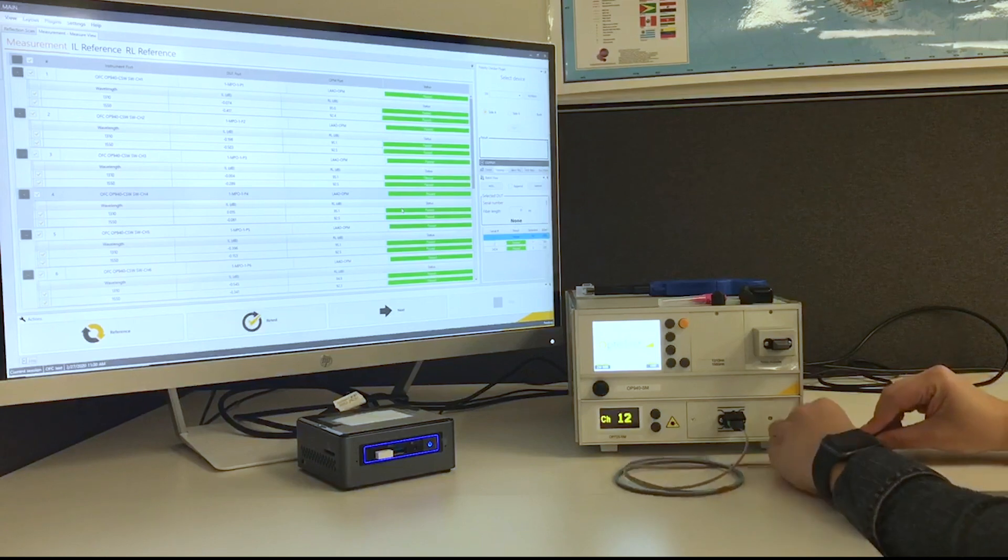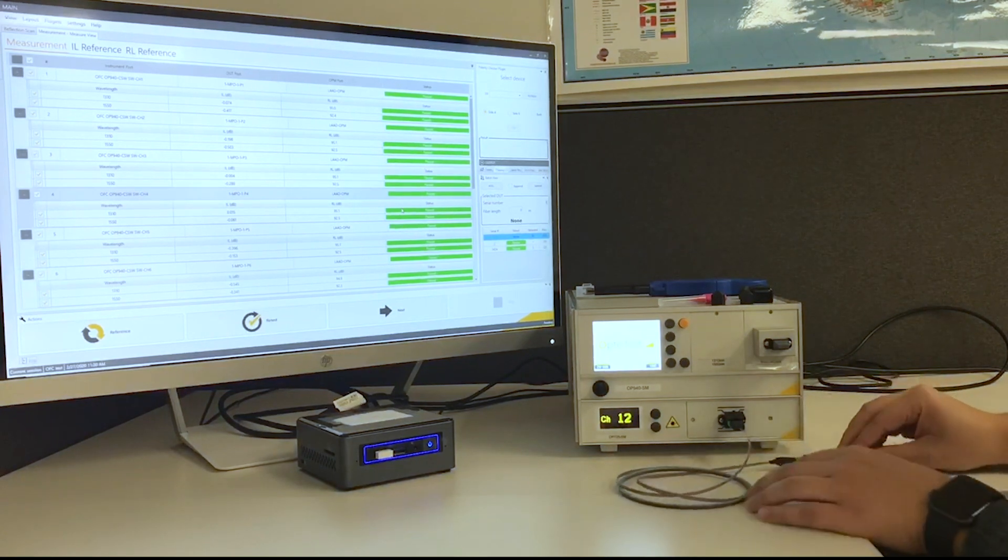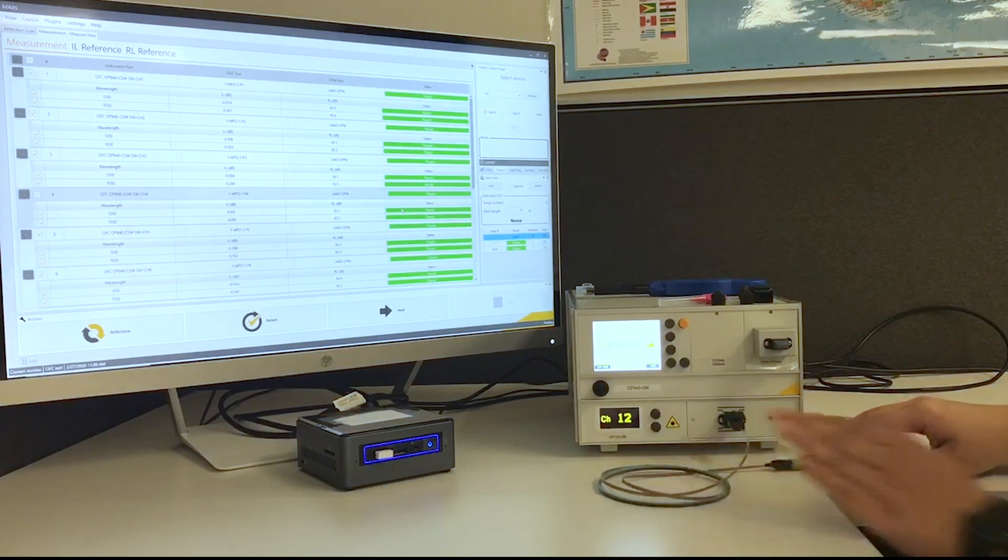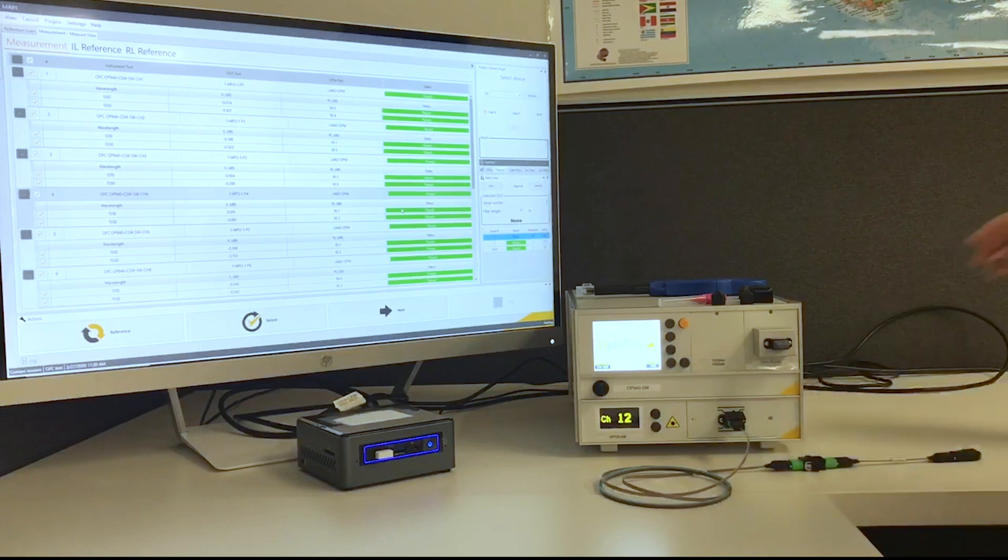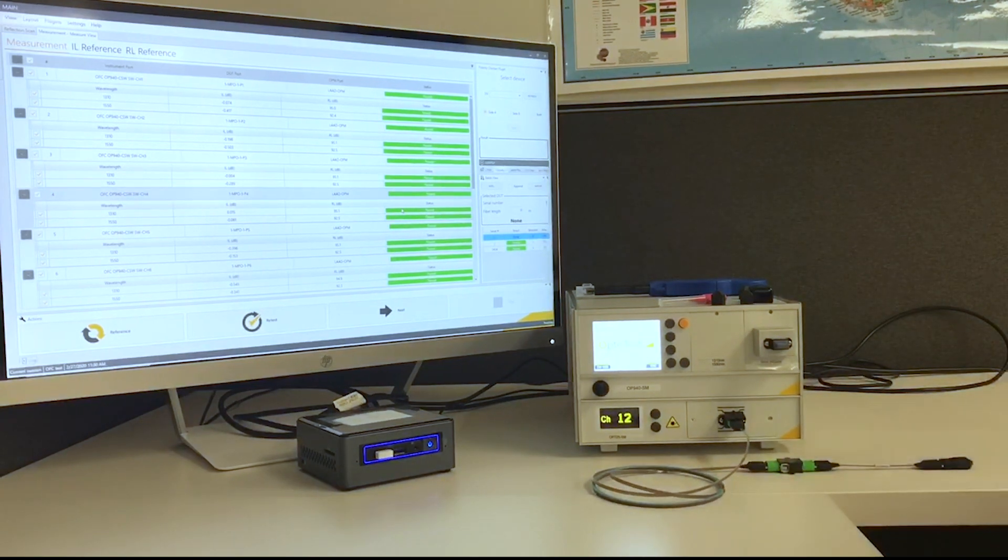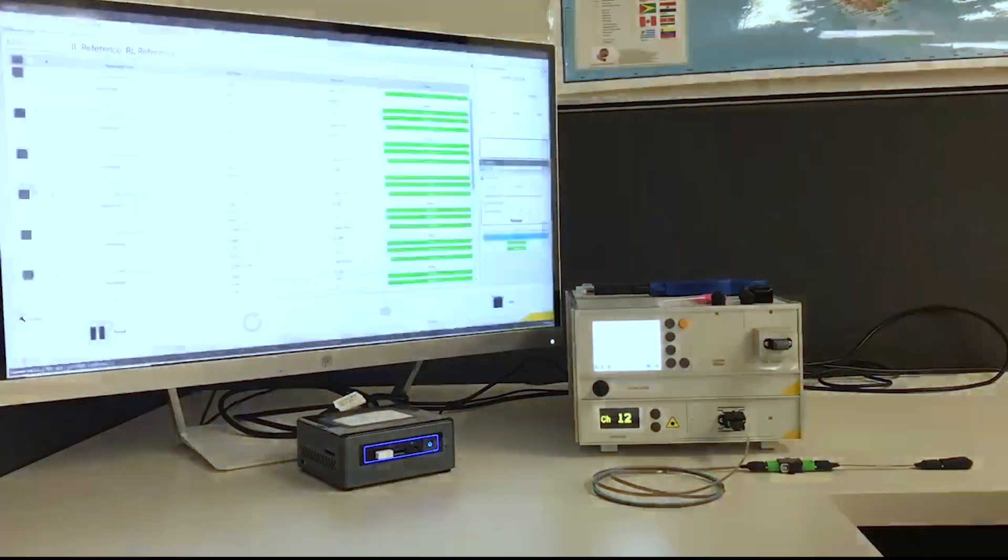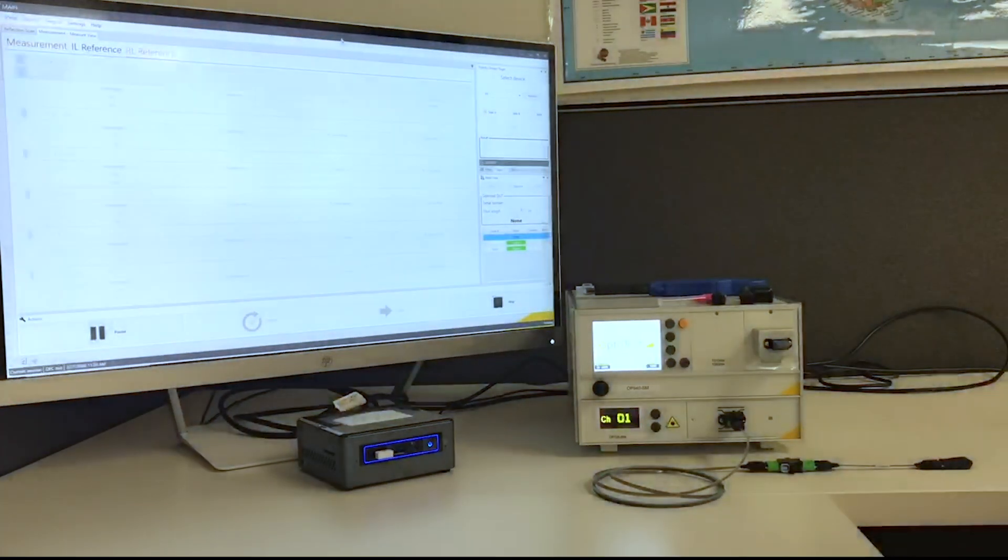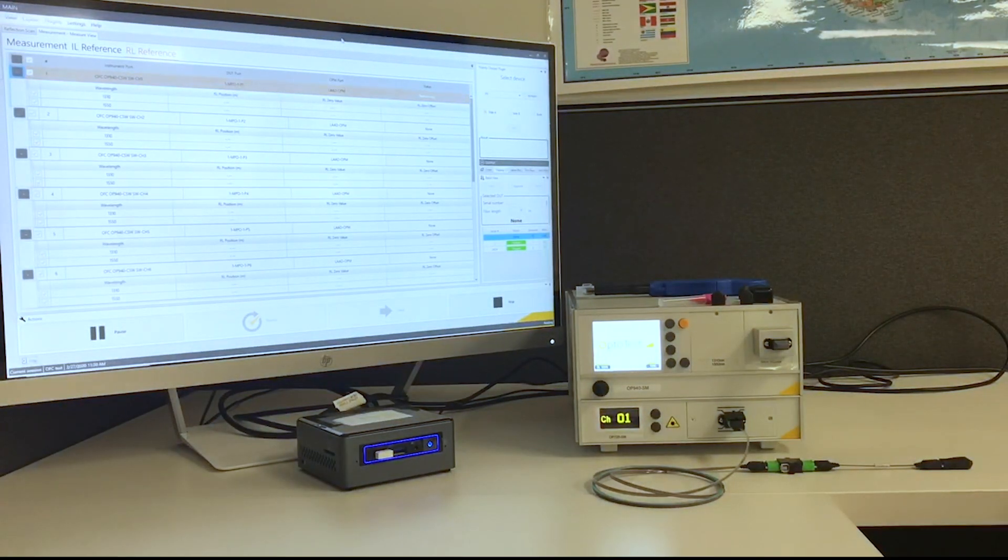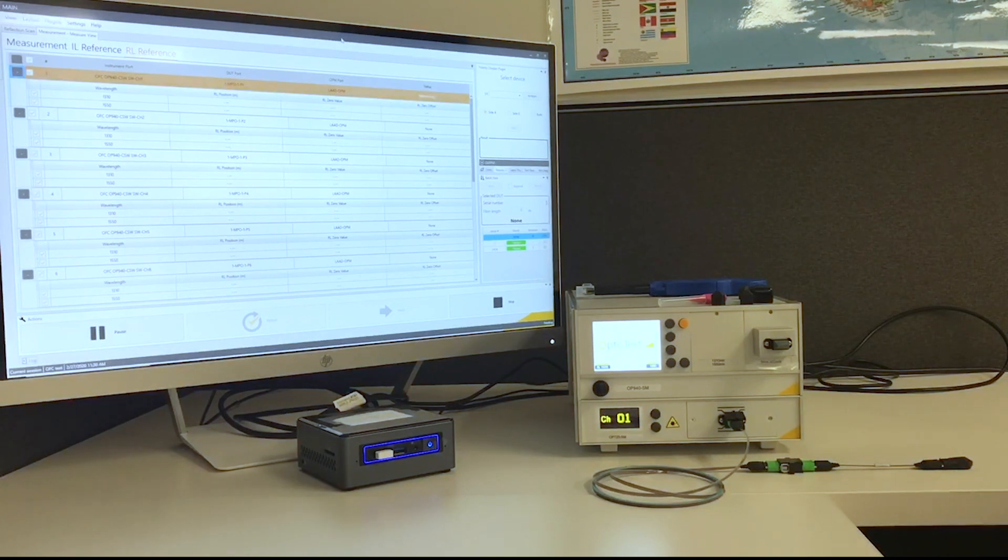So I am mating a reflector stub. This is a single mode 12-fiber cable. It's angled on the end and we want a flat polish on the end for our return loss reference. So that is the purpose of the reflector stub is to get us that flat polish. That reference is going to step through.